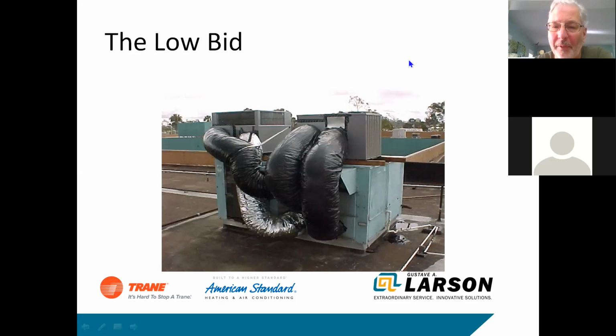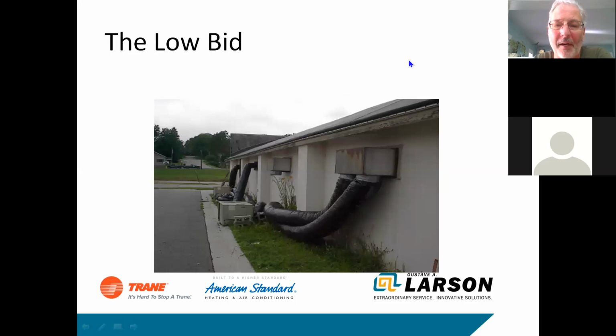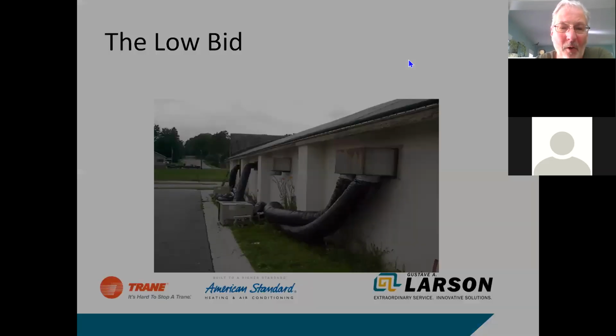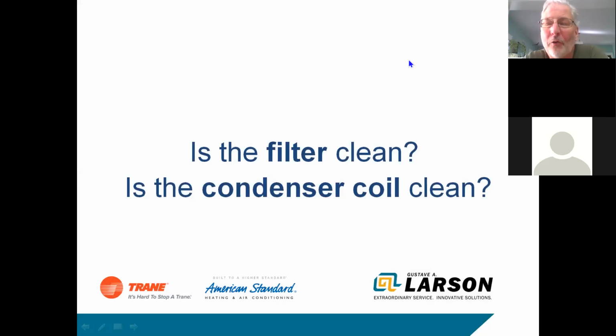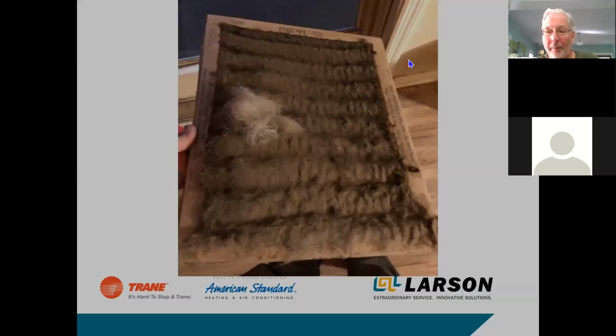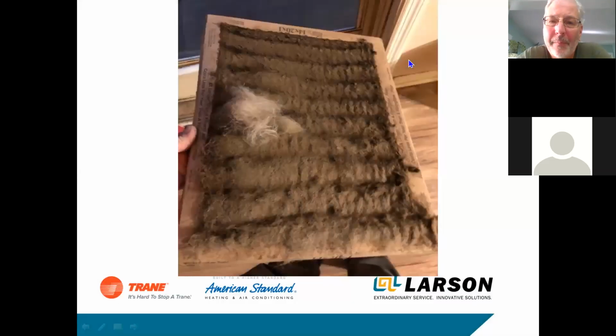That's a twin system. That's a twin rooftop. So, and then again, here's another one we call the low bid. But all kidding aside, airflow is important. Everything that we do in this industry is all wrapped around airflow. Is the filter clean? Is the condenser coil clean? Before we start adding refrigerant or before we start doing anything major to the system, make sure we've got good airflow. It's just key to everything we do.